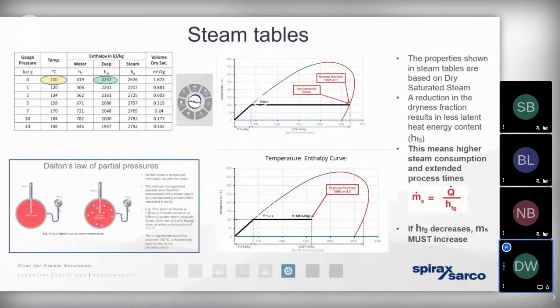We know that when steam gives up its latent heat energy, it condenses. We know that the condensate retains its sensible heat, which is around about 25% of the total heat energy. And we know that both the steam and the condensate enjoy that same pressure to temperature relationship. That's really down to the fact that when steam condenses, it gives up its energy. So there's an exchange of energy, but there isn't an exchange of temperature.